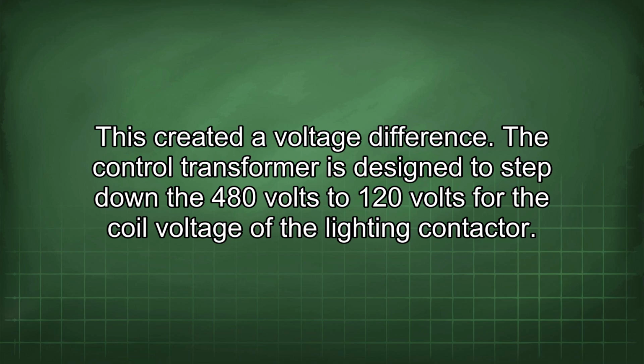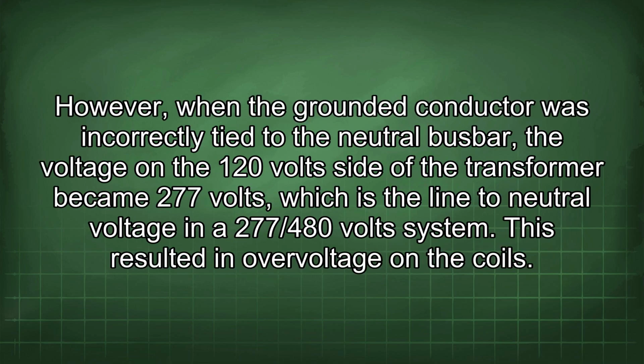The control transformer is designed to step down the 480 volts to 120 volts for the coil voltage of the lighting contactor. However, when the grounded conductor was incorrectly tied to the neutral busbar, the voltage on the 120 volts side of the transformer became 277 volts, which is the line to neutral voltage in a 277/480 volt system. This resulted in overvoltage on the coils.